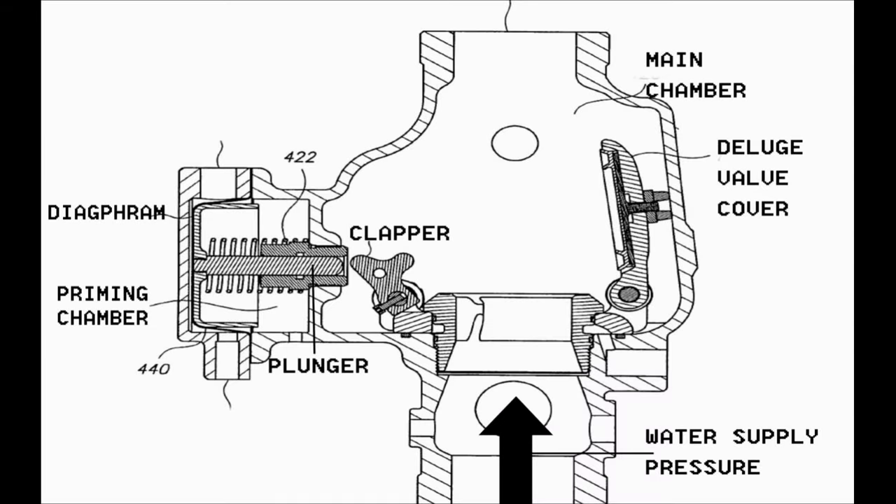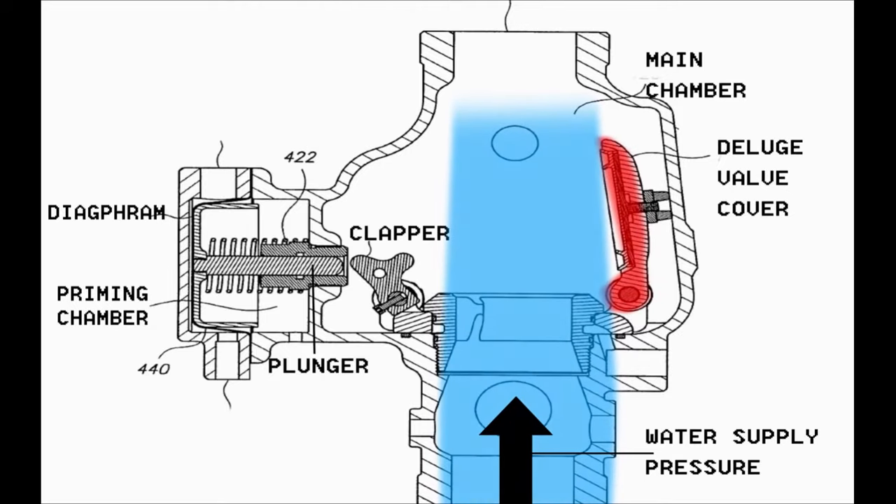In the shown figure, the release of the priming water pressure behind the diaphragm caused the diaphragm together with the plunger to move backwards, removing the pressure on the clapper, consequently opening the deluge valve by the action of the water supply pressure.